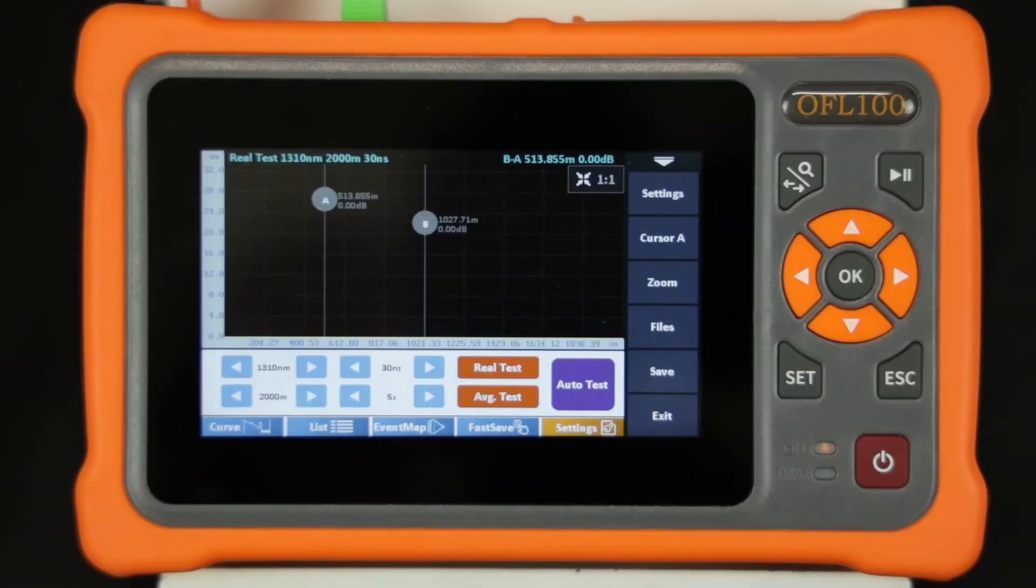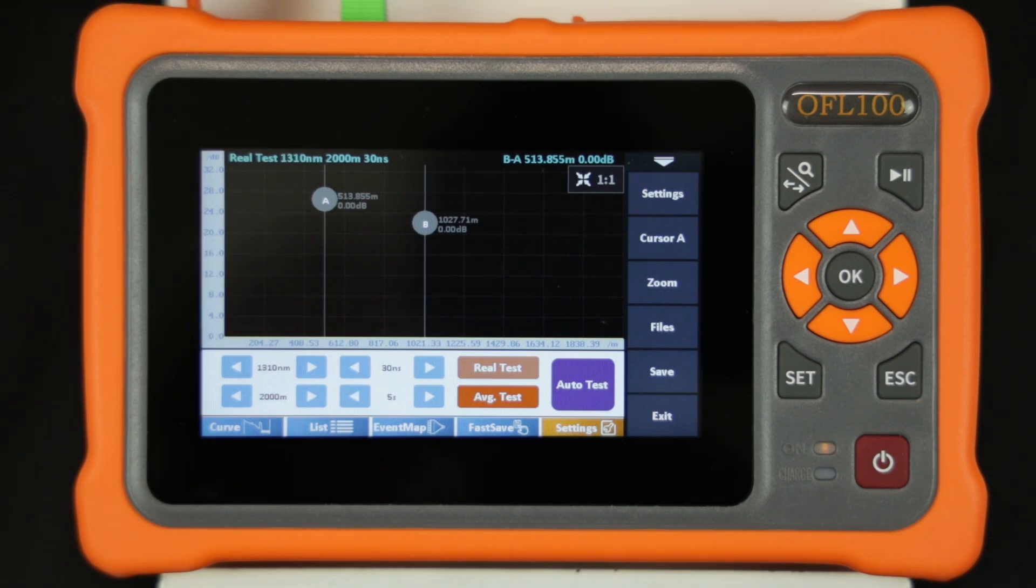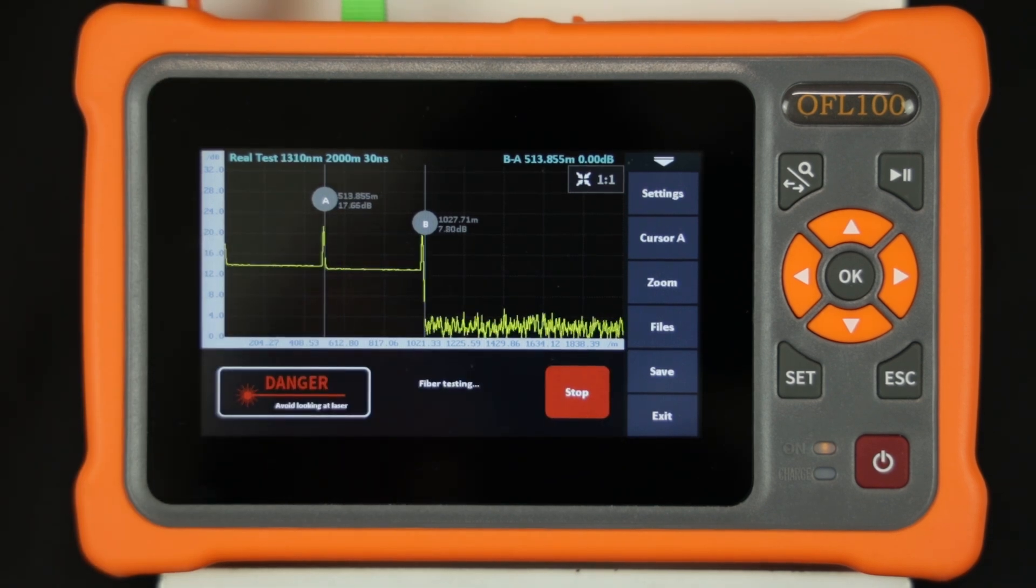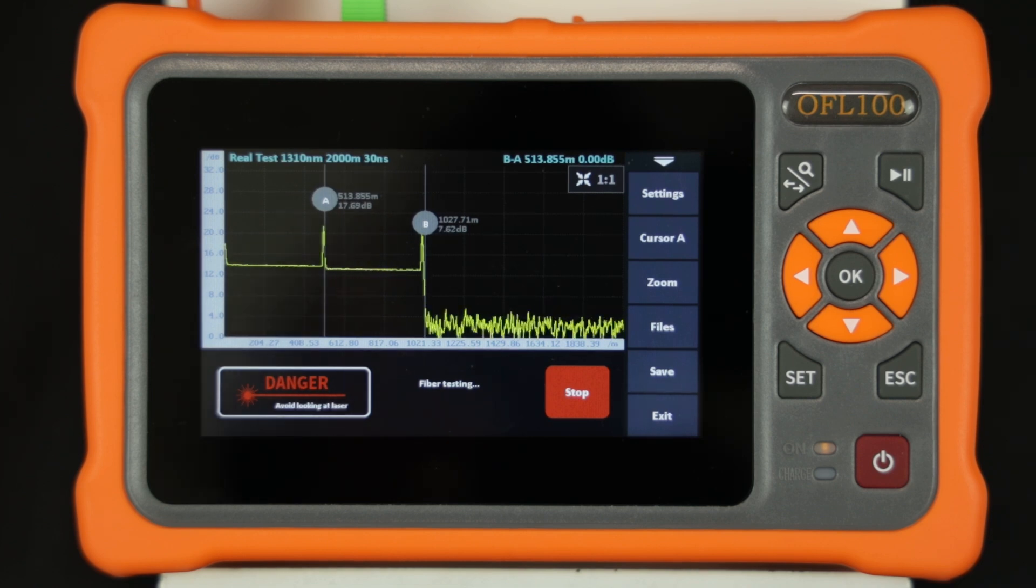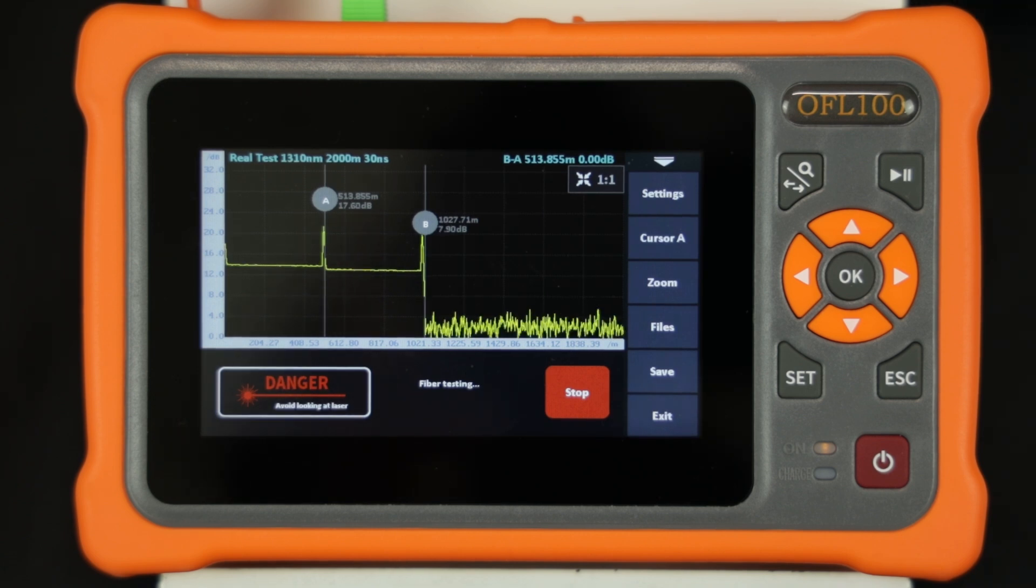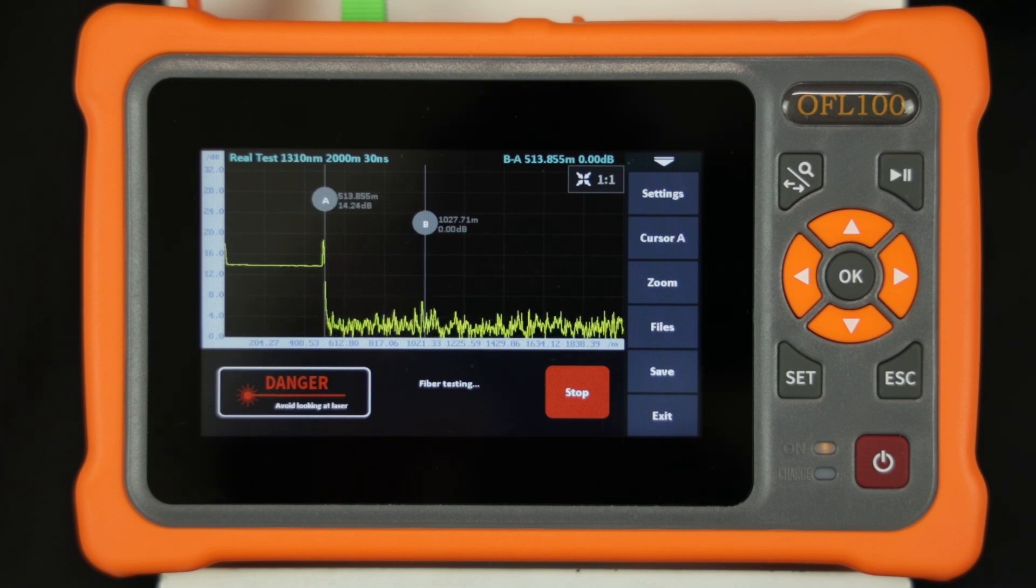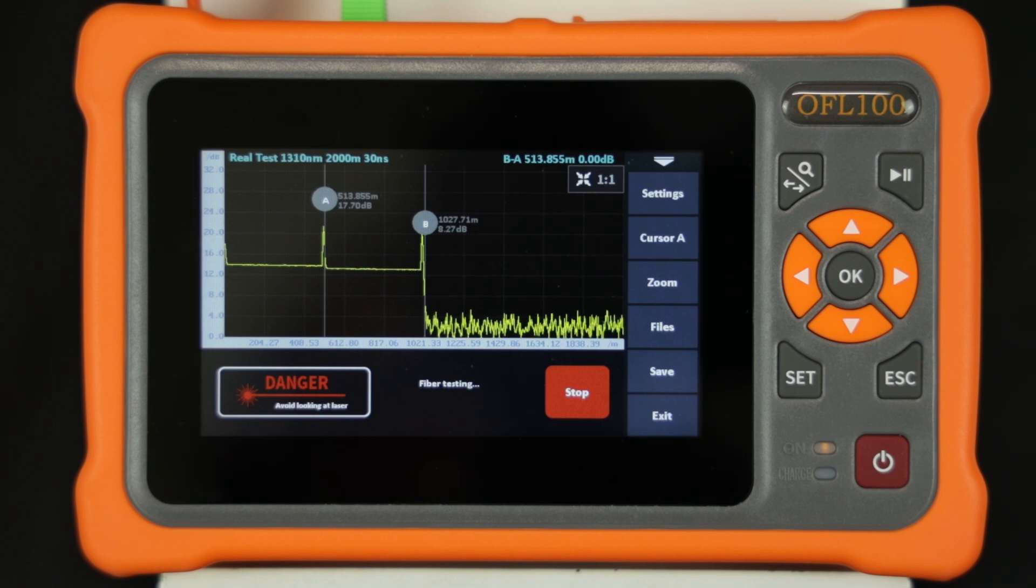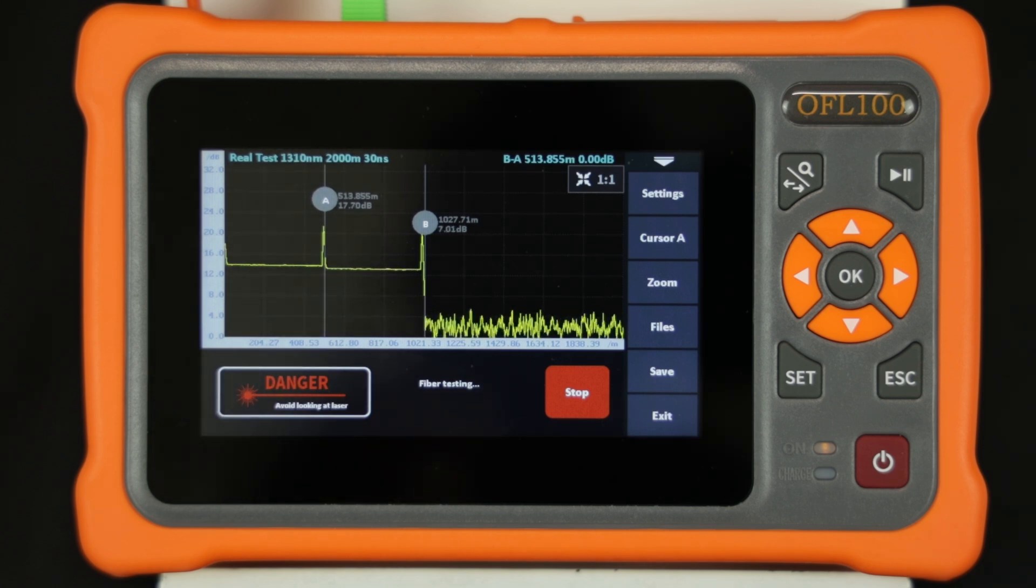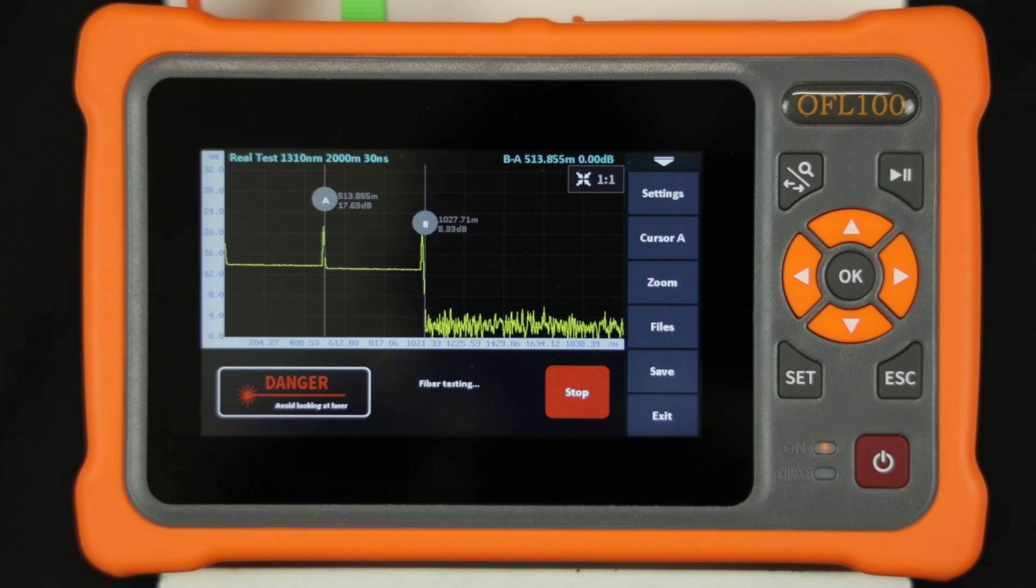Real-time averaging can be used to display the OTDR trace in real-time at an update rate of approximately 2 Hz. The real-time mode provides the technician the ability to monitor the fiber under test. Here, I pinch the fiber between the two spools at approximately 500 meter mark. Also, if the technician adds or disconnects to the fiber, they will be able to identify the effect. Pushing STOP will allow the technician to exit the real-time mode of operation.